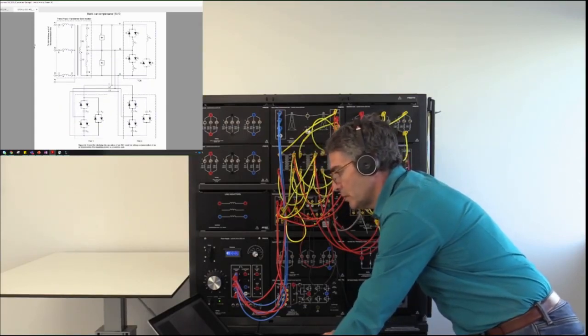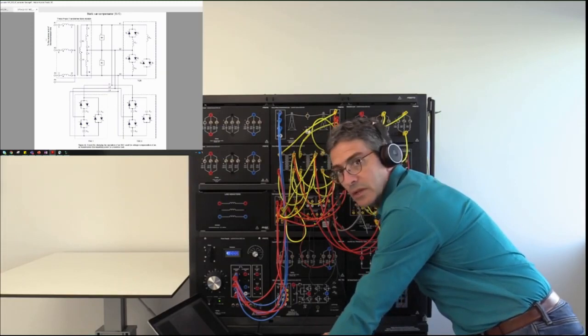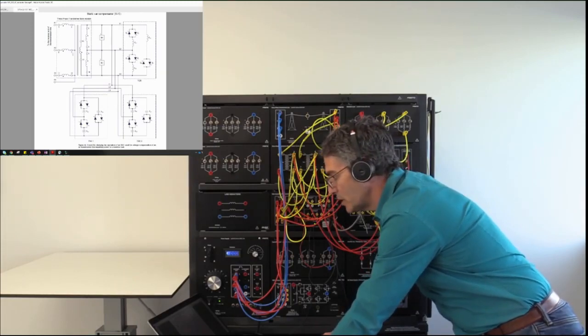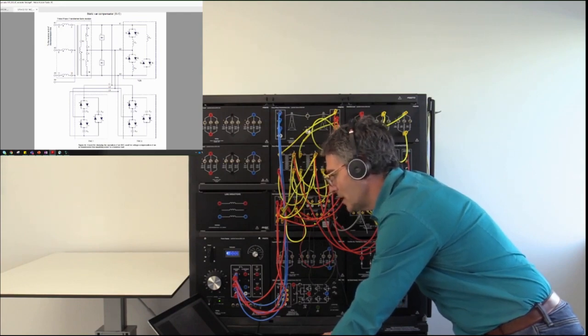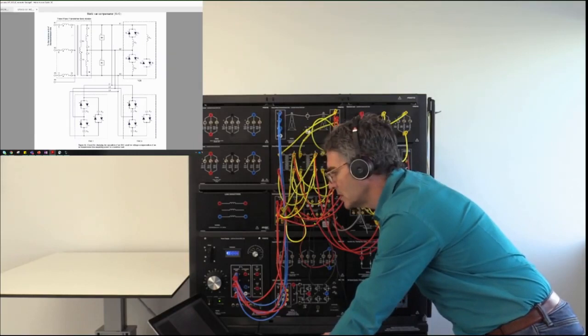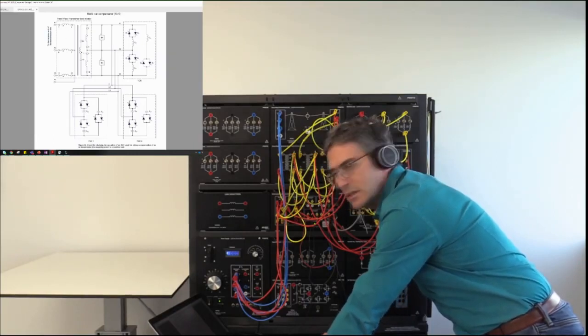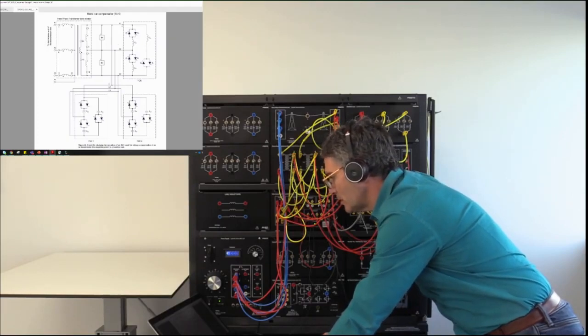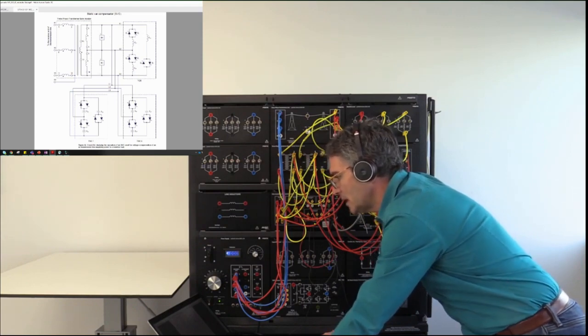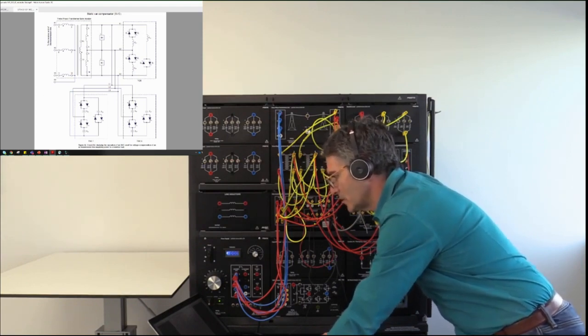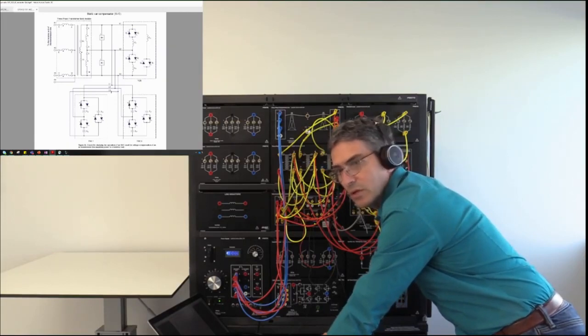A1, A2, A3, A4 arrive here on the left side, connected to the primary of our transformer. These primaries are connected in Y, while the secondaries are connected in delta. The three-phase line out of the secondaries goes to the TCR and the two TSCs, all of them in parallel with one another.